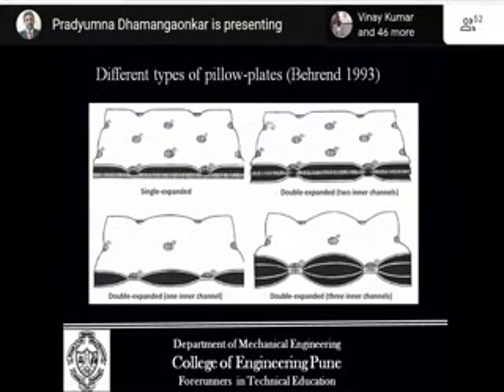There are different types of pillow plates. This is single expanded. We can go for similar metals, or two dissimilar metals can be converted into a pillow or a sort of bellows. This is the plate and this is another plate. This is double expanded, wherein here there is only one channel. But in this case it is possible to have two channels, so one channel and a lower channel. So there is higher surface area available for a fluid to flow, and thus, of course, the heat transfer rate will also be increased. This is double expanded, but only one channel.